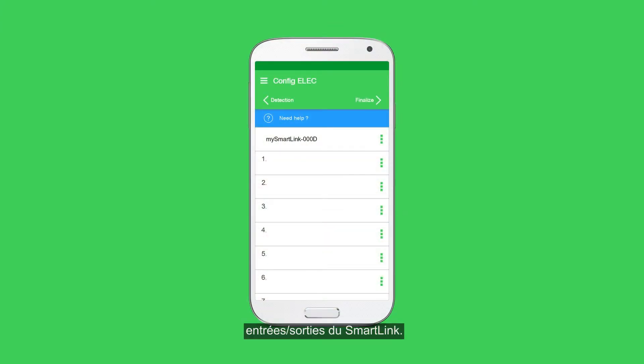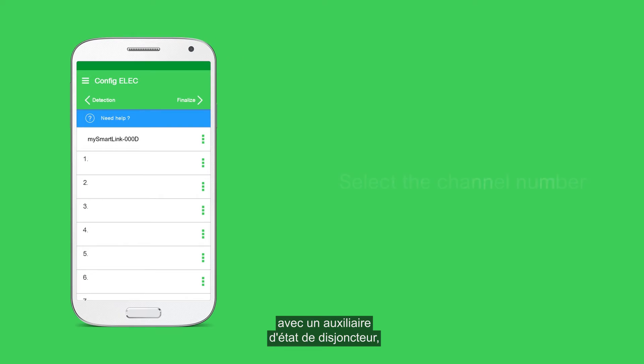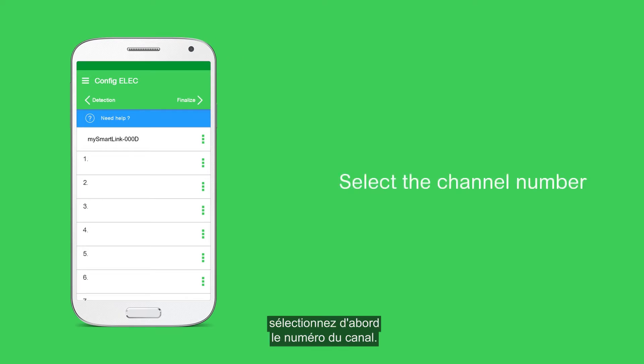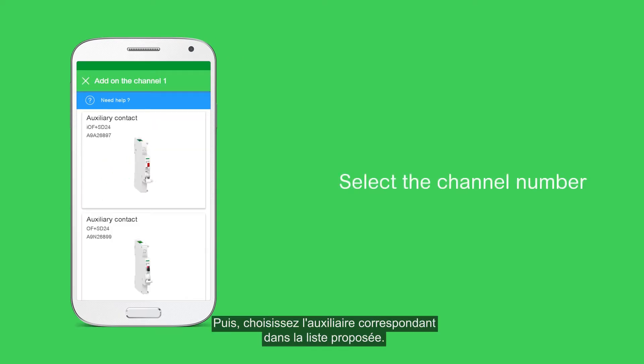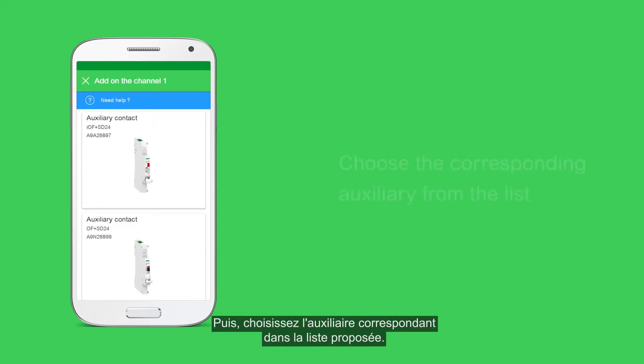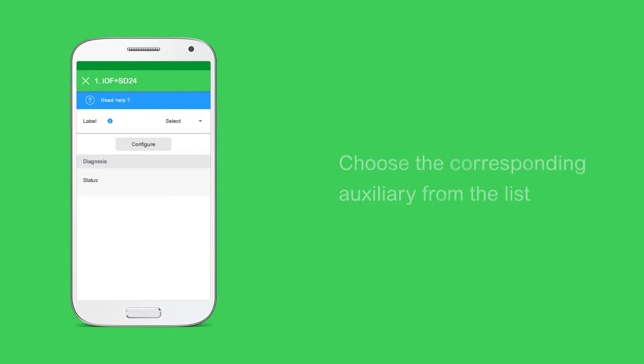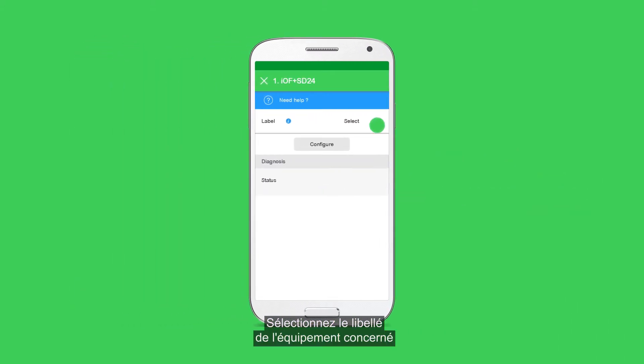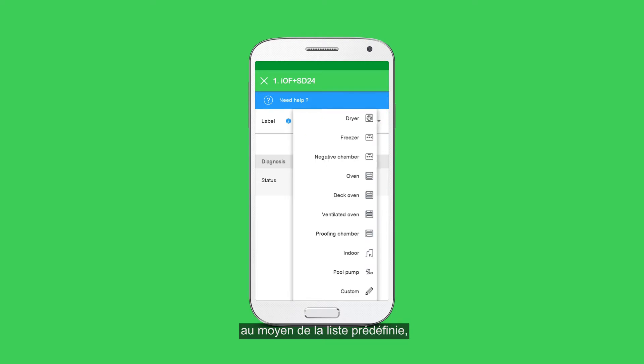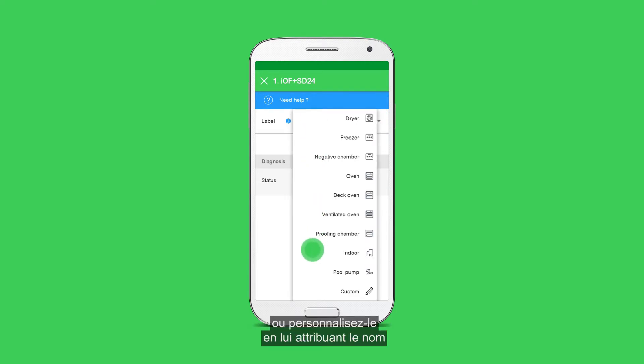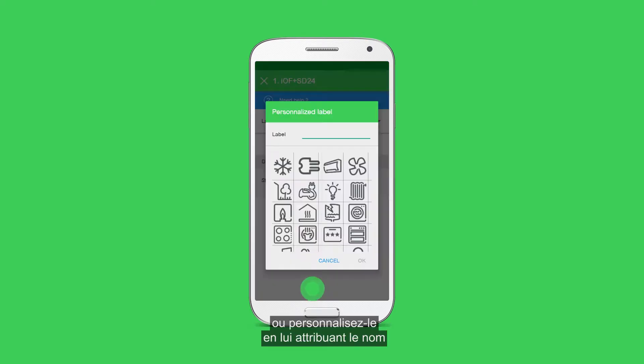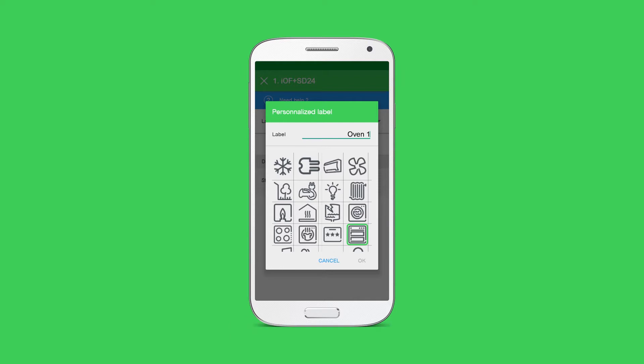You can now configure the different inputs and outputs of SmartLink. For example, to configure Channel 1 with a breaker status auxiliary, start by selecting the channel number, then choose the corresponding auxiliary from the list. Select the label of the related equipment from the pre-defined list, or customize it by giving it a name and an icon of your choice.